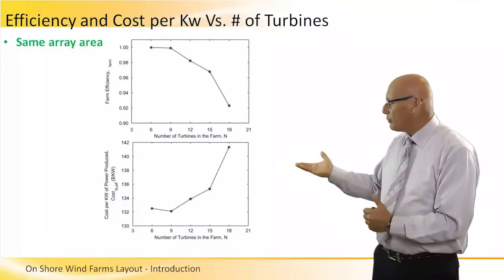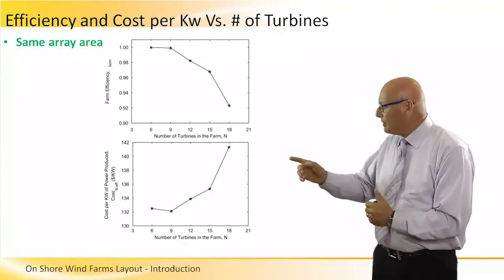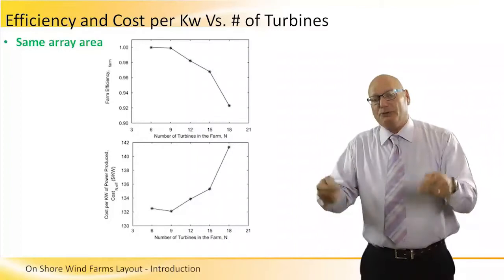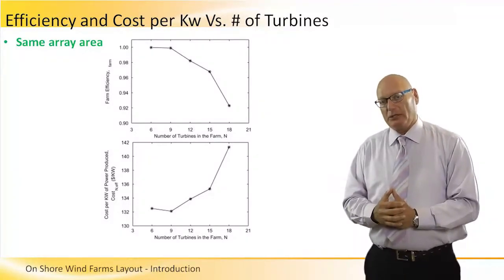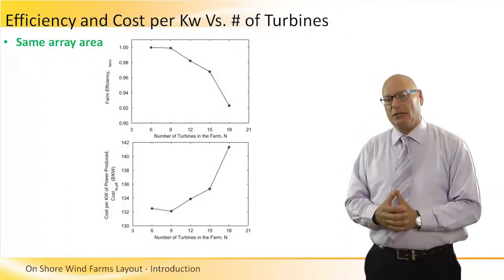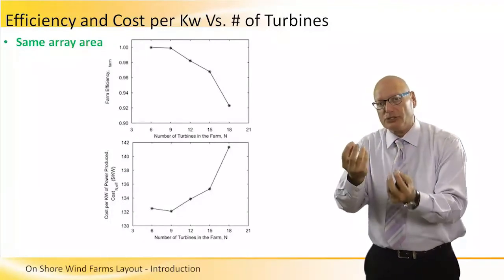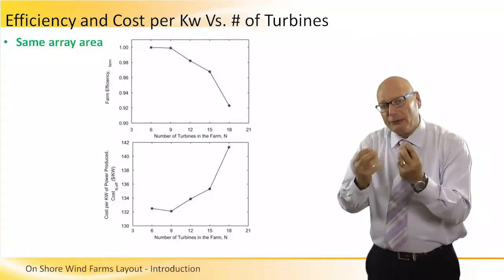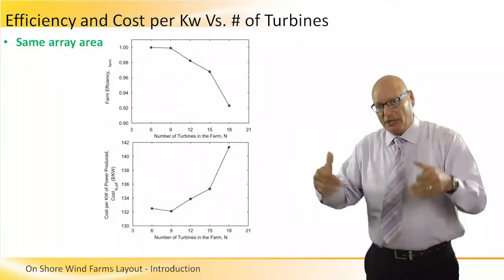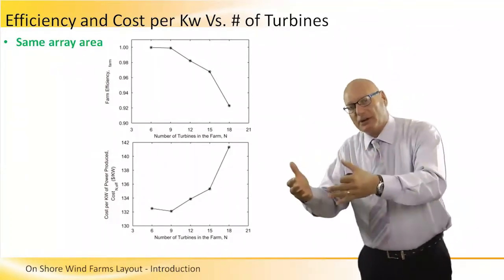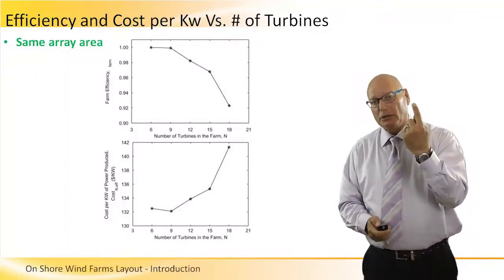The bottom graph shows cost per kilowatt for the same land area as we vary the number of turbines. Not only does efficiency decrease as we add turbines, but the cost per kilowatt also goes up. So we produce more electricity, but each kilowatt costs more. There is a trade-off in the cost-benefit computation of adding more turbines in a given area — adding more turbines does not necessarily mean more output production, as efficiency goes down and cost per kilowatt goes up.